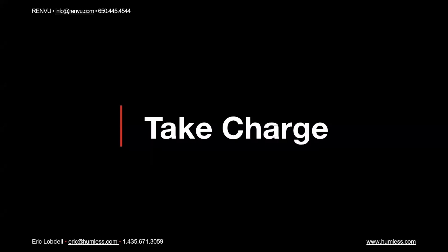So the first question for you, if you're ready: does the 10.4 have an integrated auto transfer switch? Two transfer switches are built into the 10.4. One is for the grid and one is for a generator feature. But if not using a priority loads panel, you would need to put in an exterior transfer switch due to the fact that we can't backfeed the grid.